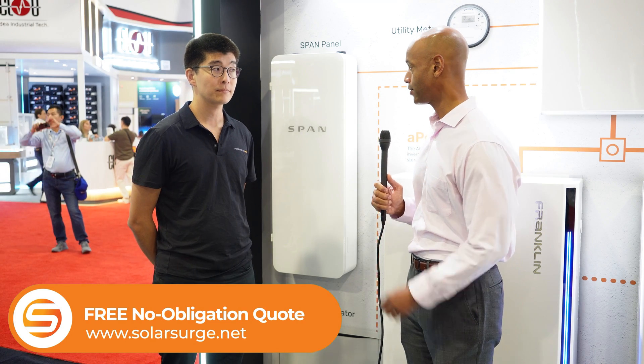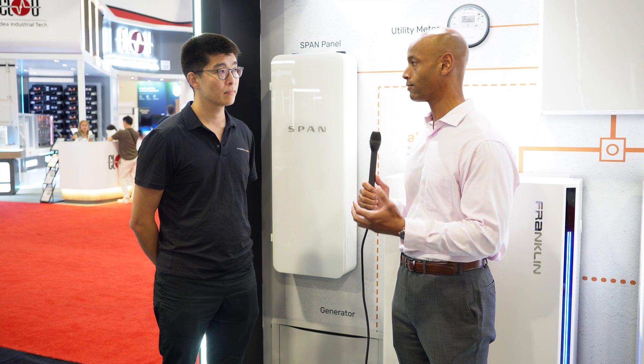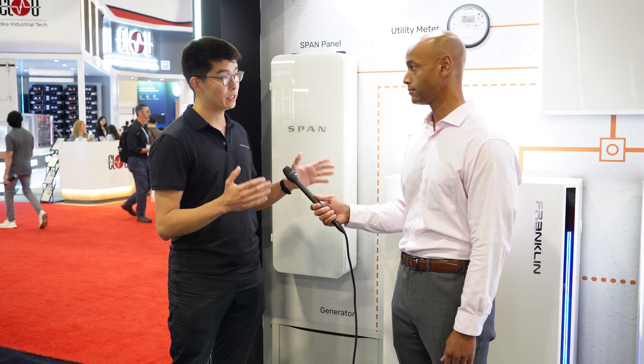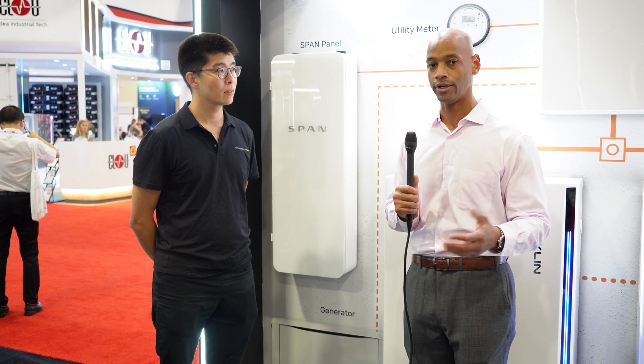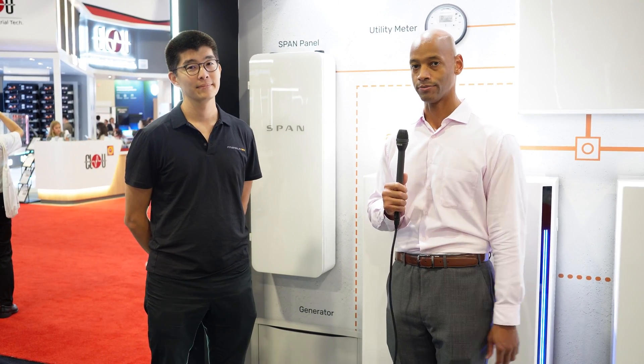Is there anything else the audience should know about how the SPAN and Franklin systems communicate or work together to give you a longer-running battery? Sure. It's local communication. So when there's a long-duration outage, a big storm, or you lose Internet, you don't need to rely on Wi-Fi or Ethernet. You have a direct LAN cable from your SPAN panel to the aGate. It's very resilient. That's an important point — we don't want to be dependent on an app or the Internet for these systems to work, especially in a crisis or emergency.